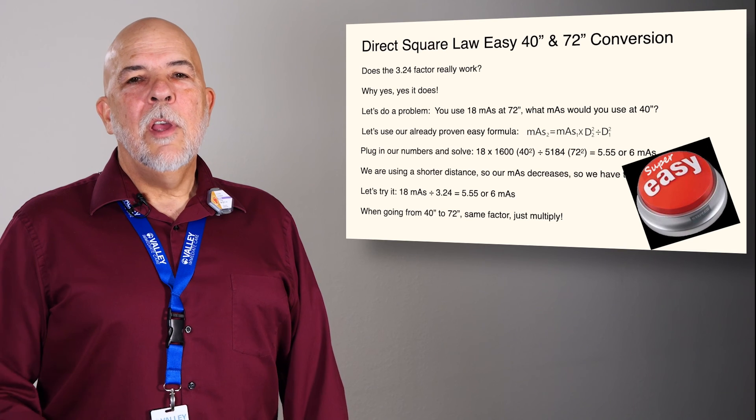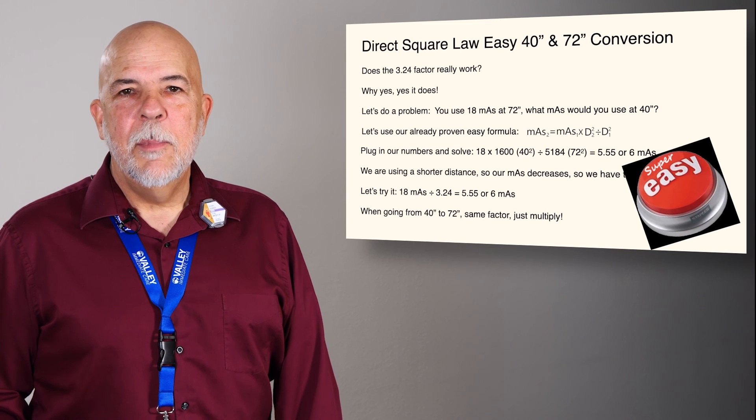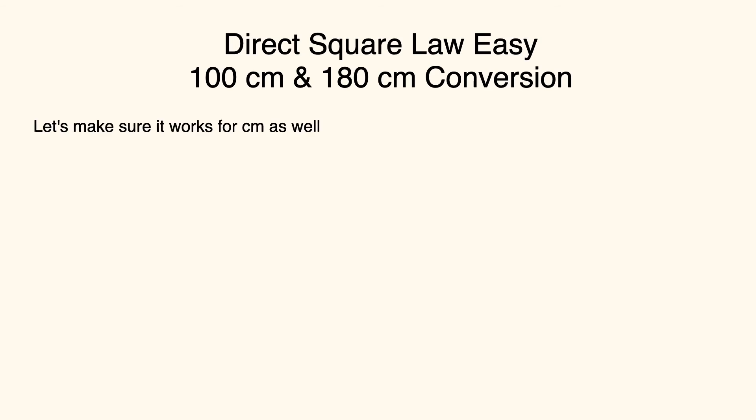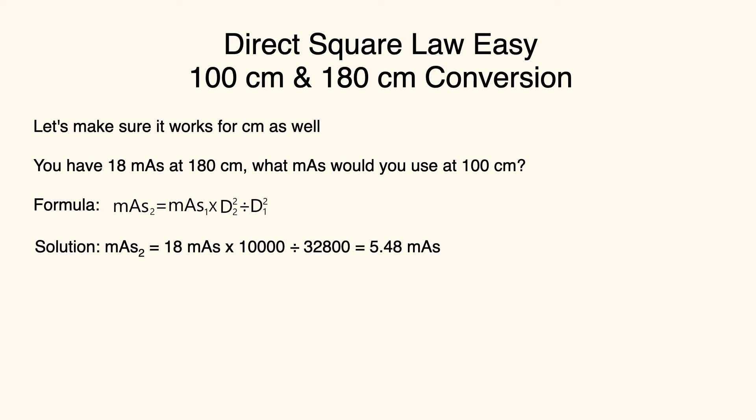So does this work at 100 and 180 centimeters going back and forth? Absolutely. We have 18 mAs at 180 centimeters. So what mAs would we need to use at 100 centimeters? Using our already proven formula, we come up with 5.48 mAs.